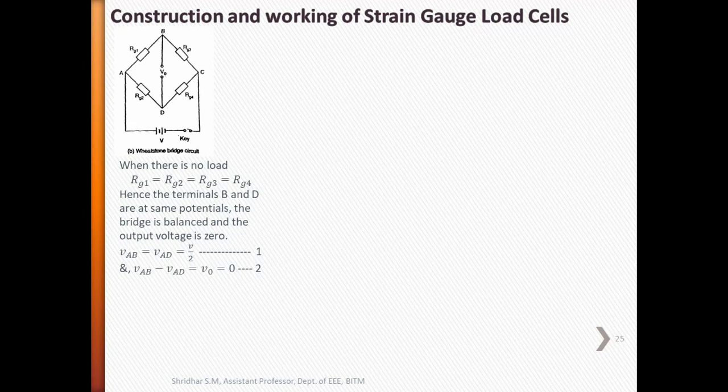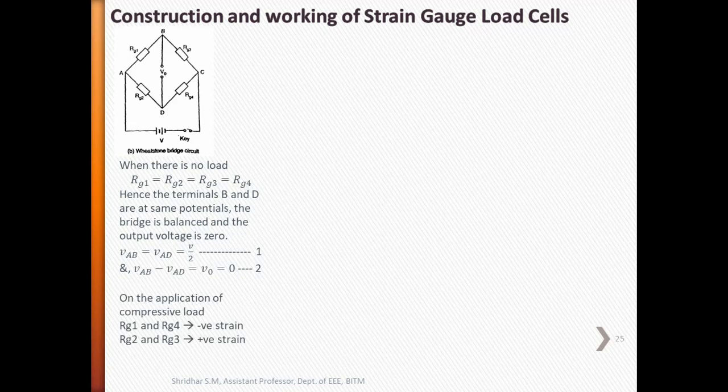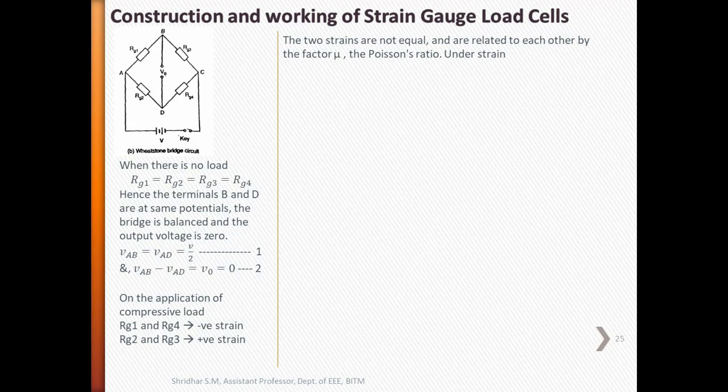Now, on the application of compressive load to the unit, the vertical gauges RG1 and RG4 undergo compression, that is negative strain, and there is a decrease in resistance. The circumferential gauges RG2 and RG3 simultaneously undergo tension, that is positive strain, leading to increase in the resistance. The two strains are not equal. These are related to each other by the factor mu, which is the Poisson's ratio under strain.